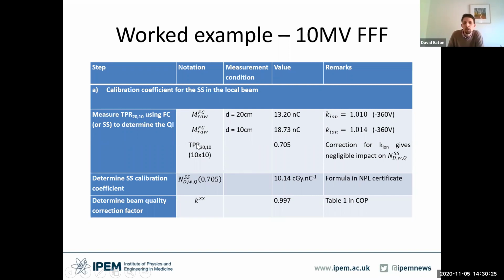So we measure our TPR 20/10. We've got a reading at 20 deep, a reading at 10 deep, and we take the ratio of those to give our TPR. Now we need to be careful because the ion recombination will be different for a different dose rate and therefore for a different depth in the material. But we also recognize that in this situation, although the difference is substantial, 0.4%, actually when you relate that through to the calibration coefficient, it has negligible impact on the calibration coefficient. So it's not necessary to correct your TPR readings for ion recombination. It is more accurate to do so, but the impact on the final result is probably going to be very small.